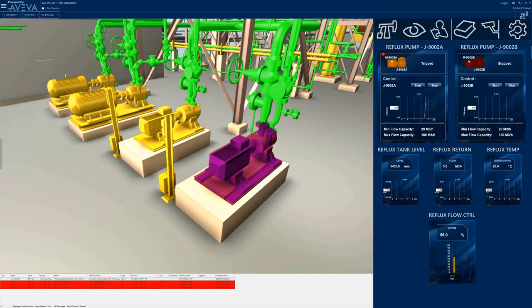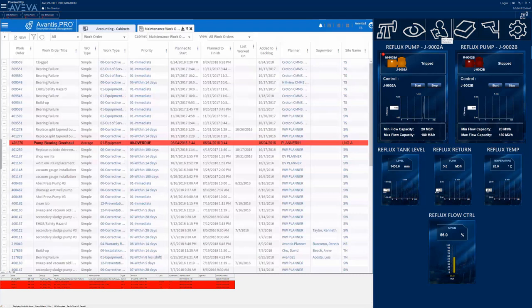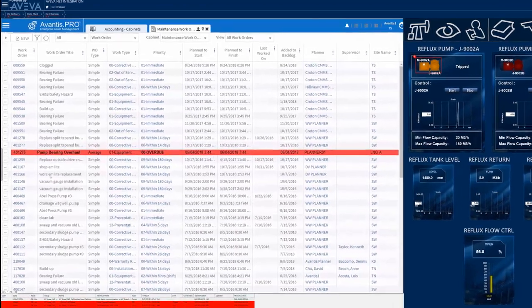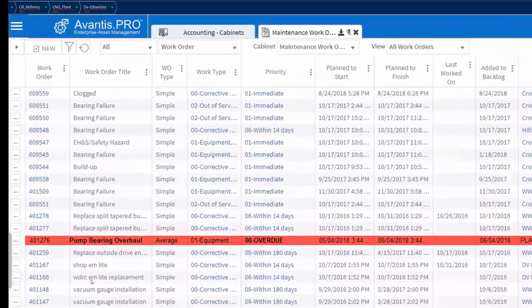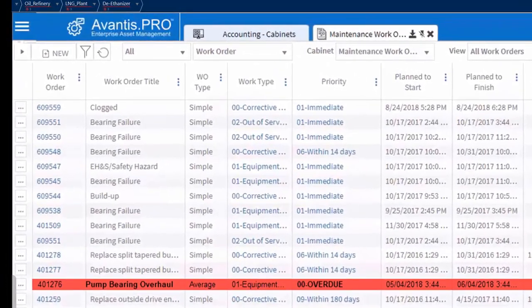Now that the operator is satisfied that J9002B is, in fact, a viable backup pump, they check one last place to make sure that it's okay to start the pump – the maintenance system. Selecting the Avantis icon in the integration menu brings in a display of the maintenance records for all of the items in the currently selected area.